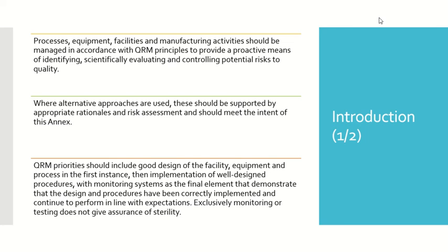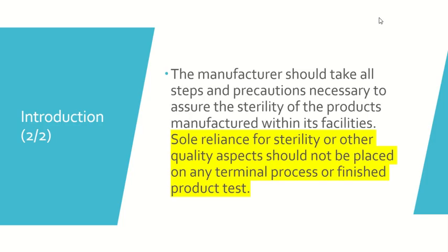Exclusively monitoring and testing does not give assurance of sterility. Just remember, extensive testing cannot assure the sterility of your product, right? We'll come to this point later on as well, but keep in mind testing cannot suffice for the issue of sterility, right? The manufacturer should take all steps and precautions necessary to assure the sterility of the product manufactured within the facility, right? So that is what I was talking about in my last slide as well.